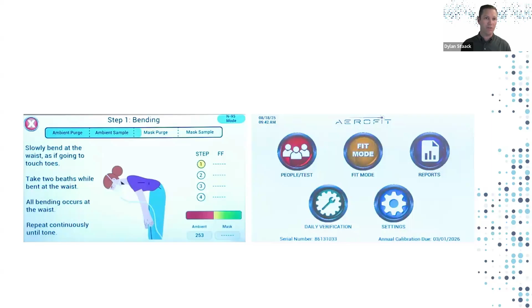So we've talked a little bit about particle generation management, and I really loved this picture and wanted to show it because it shows that we're creating that test environment close to the instrument. Other fit test machines ask you to put that particle generator at a minimum of 10 feet away and create this huge environment of particles. What that does is, when you're not fit testing, you're taking a lot of particles into that unit that you don't actually need to.